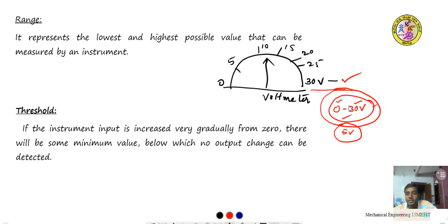One more important thing we want to consider in the range of the instrument. For example, 0 to 30 volts. If I want to measure 5 volts every time, is it okay to choose this instrument? No, this is not okay. While choosing an instrument with a 0 to 30 volts range, our values should fall in the 60% range. 60% of 30 volts means around 15, 20, somewhere around here. If we want to measure 10 to 25, that is okay for this instrument. So it represents the lowest and highest possible value that can be measured by the instrument. That means 0 to 30 volts is the range of the instrument.